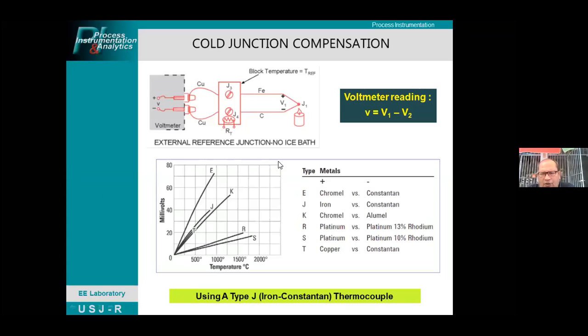These types of metal produce a relationship between temperature and millivolts, as in the graph. Chromel versus constantan, iron versus constantan, chromel versus alumel, and so on. So we first call these different metals. Combining these metals, we identify a positive component and a negative component metal, combining them to form these thermocouples. Where I mentioned earlier the type K thermocouple, it is chromel versus alumel.